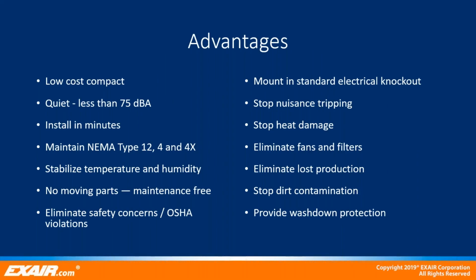Why should you consider a cabinet cooler system over another method of cooling? Well, the advantages are pretty clear. They're low cost, they're compact, they're quiet, they install in minutes, and they can maintain your NEMA 12, 4, and 4X cabinet rating. They stabilize temperature and humidity, no moving parts, so they're maintenance free. They eliminate any safety concerns or OSHA violations. They mount in standard electrical knockouts. They stop nuisance tripping, stop heat damage, eliminate fans and filters, eliminate lost production, stop dirt contamination, and provide washdown protection.